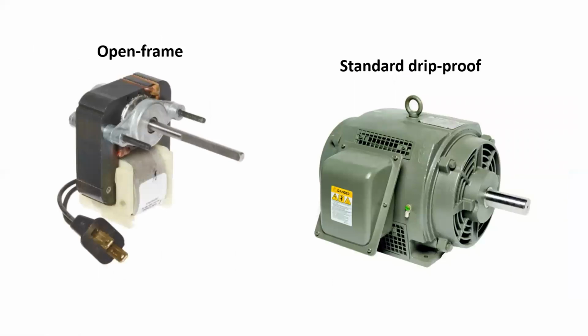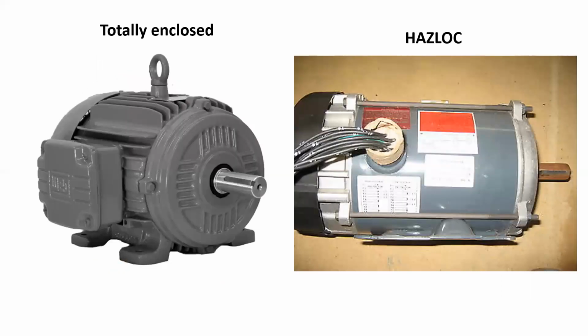There's lots of different types of constructions when it comes to squirrel cage motors. We have open frame, and obviously the one on the left here is not a true three-phase motor, but the term open frame is a relevant type of motor construction, usually utilized within manufactured equipment, not something an electrician would install. We have standard drip-proof motors, which are only intended to withstand condensation or dripping of liquids. We have totally enclosed motors, which are, I would say, one of the more common applications, especially in the industrial sector. And then we have hazardous location motors, which are a step above a totally enclosed. And these would be utilized in areas where we are exposing the equipment to an explosive gas atmosphere.